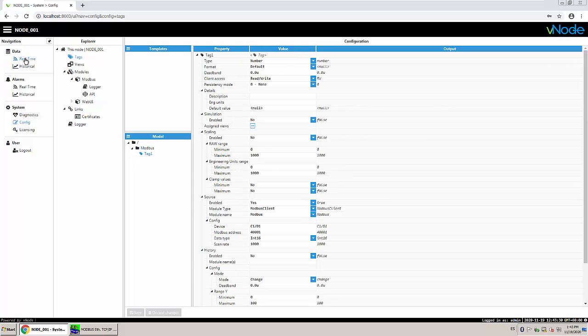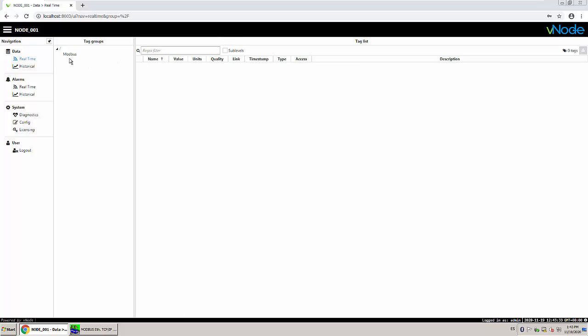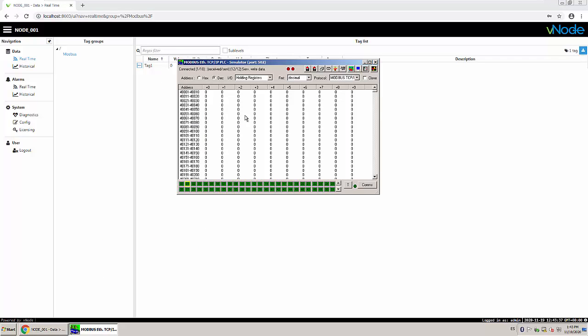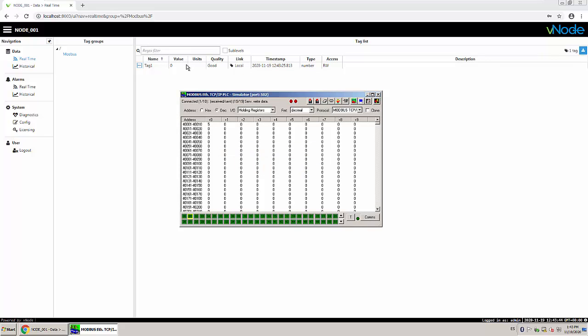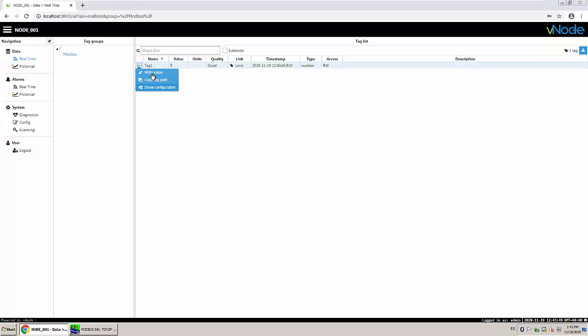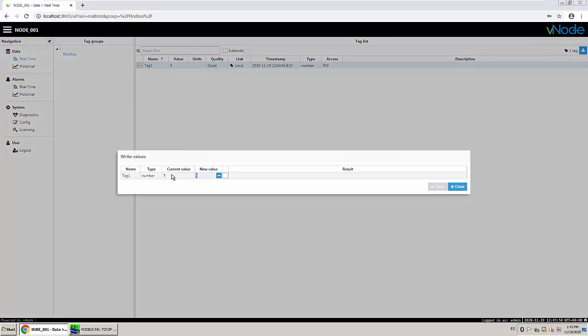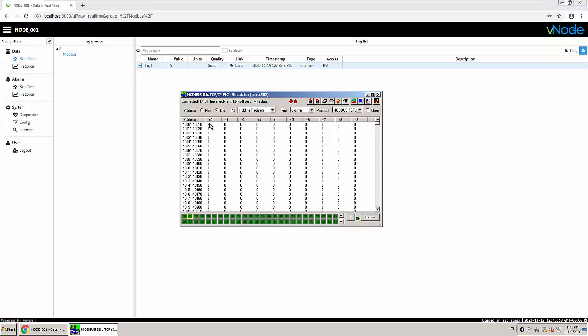I already have tag one. Let me check if I'm actually reading something — yes, I have a zero. This zero should be at address 400001. If I change it here we should see a change in the tag, and also the other way around — if I change the value here we should see a change in the Modbus device. We are reading and writing — perfect.